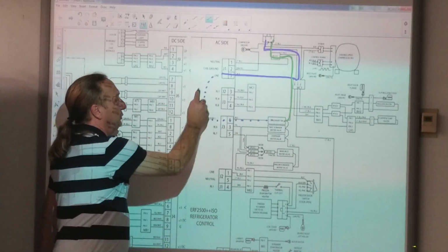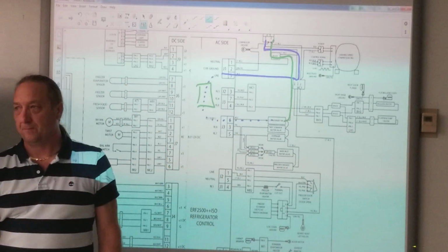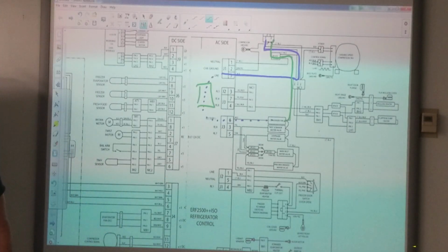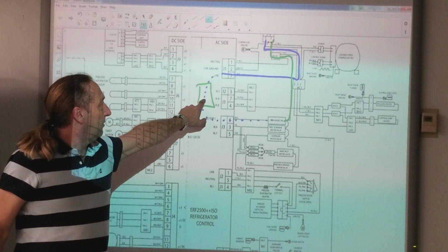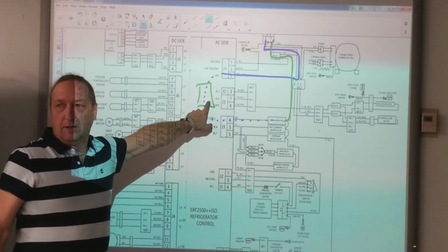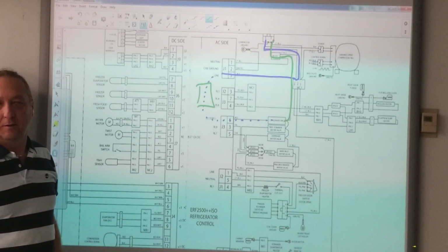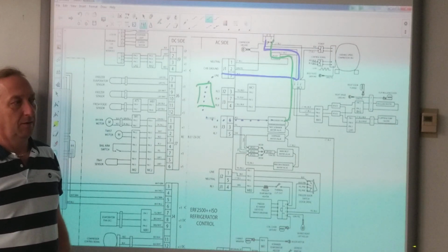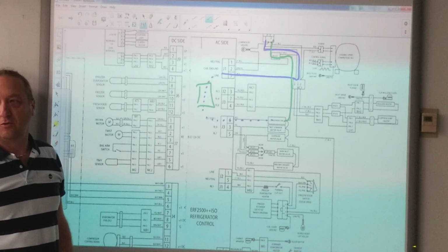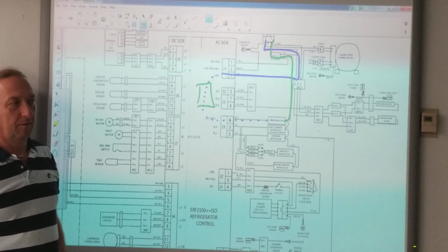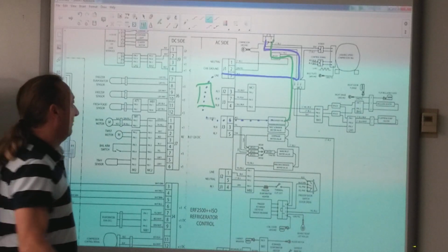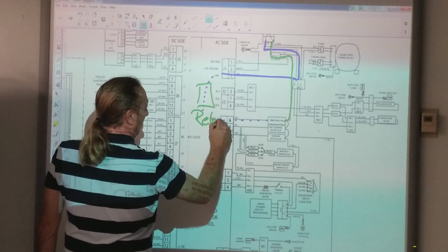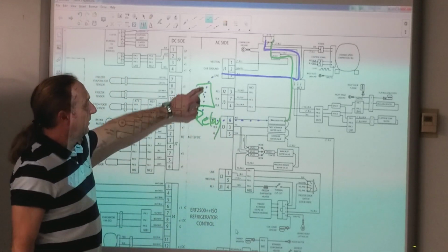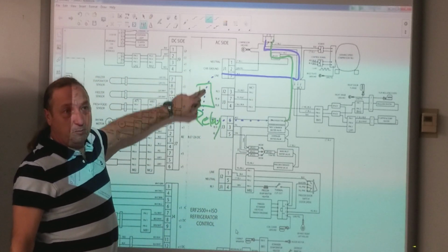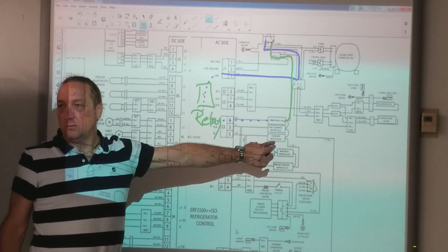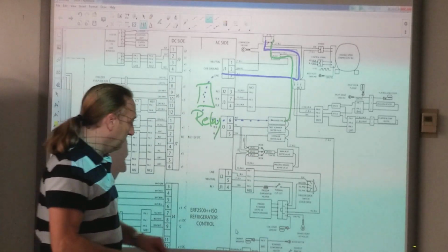So there's some sort of component here, what would we find? It's the board. But what would be on the board there? We talked about it yesterday, not a transformer, relays. There'll be a relay on the board. Power coming into the board, this relay sends power back out. When that relay closes, that unit will run.